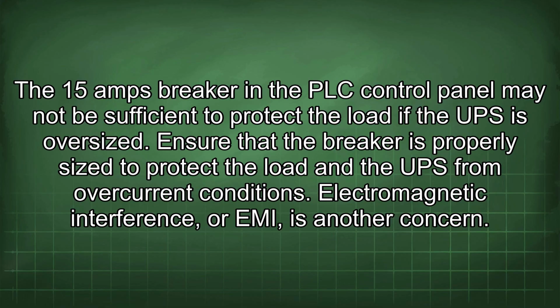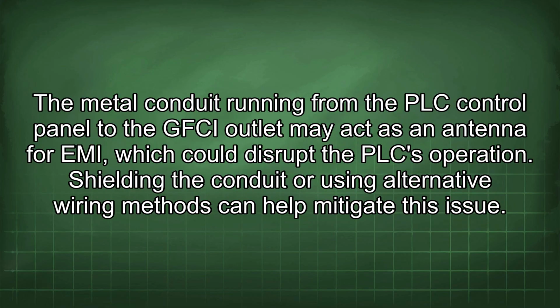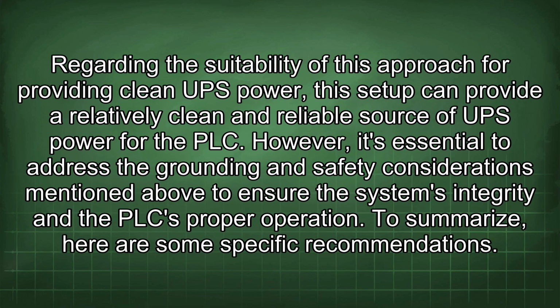Electromagnetic interference, or EMI, is another concern. The metal conduit running from the PLC control panel to the GFCI outlet may act as an antenna for EMI, which could disrupt the PLC operation. Shielding the conduit or using alternative wiring methods can help mitigate this issue. Regarding the suitability of this approach for providing clean UPS power, the setup can provide a relatively clean and reliable source of UPS power for the PLC. However, it's essential to address the grounding and safety considerations mentioned above to ensure the system's integrity and the PLC's proper operation. To summarize, here are some specific recommendations.